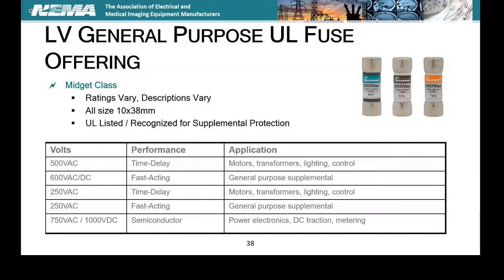Again, you're going to want to consider what load you're on. You've got the Charlie Chaplins. These are your midget class fuses, I like to call them. Yep, those are your midget class fuses, and they're just smaller. Again, the voltage rating and the amp rating that they'll go up to are all critical and important parameters that you'll have to consider for the application that you're working on. You can probably go to the next slide.